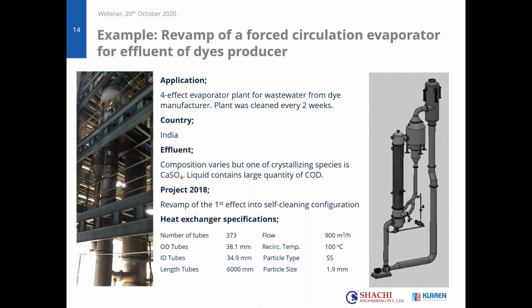In terms of mechanical layout, and because that's the second thing we have to look at, is there space to integrate our components? We also found the possibilities to do this. Because at the end, and you can see that on the right picture, maybe I can show it with the spotlight. On the right picture, you see how the situation looks after the revamp. So we have installed as an additional part the particle separator in between the calandria and the vapor liquid separator. And by this downcomer, we recirculate the particles. And here you see the recirculation to the pump. So also from the mechanical layout, it was possible.